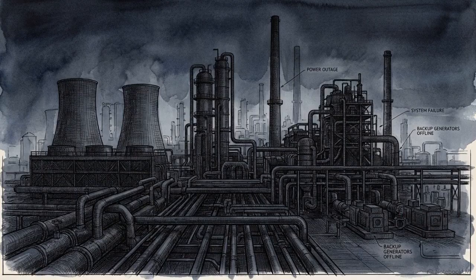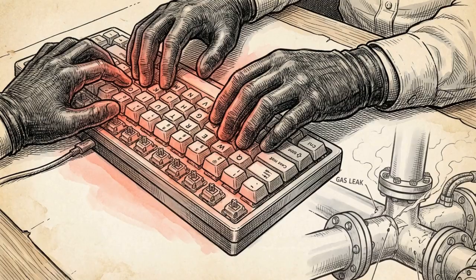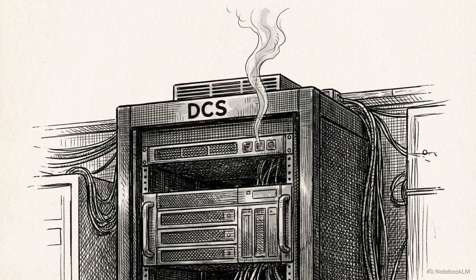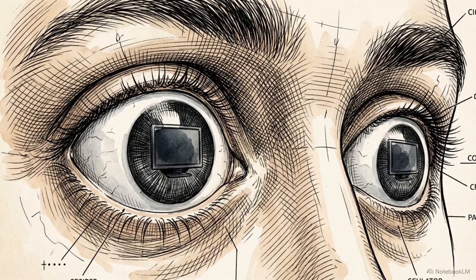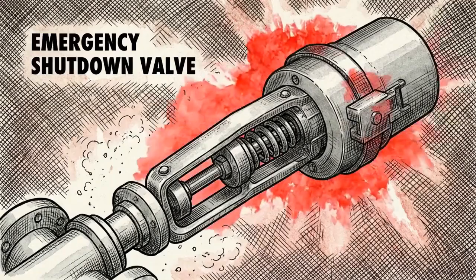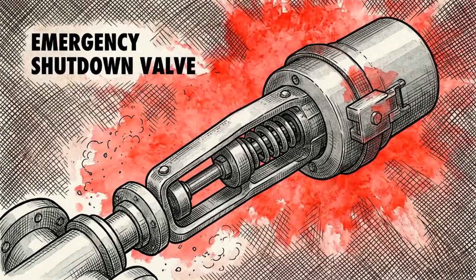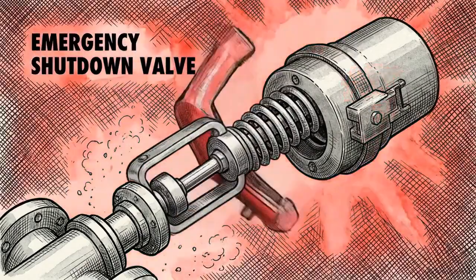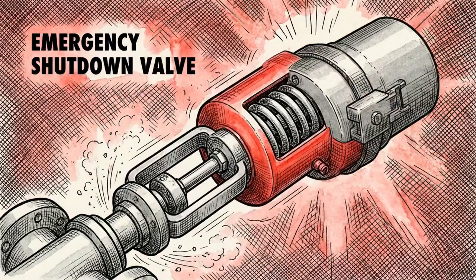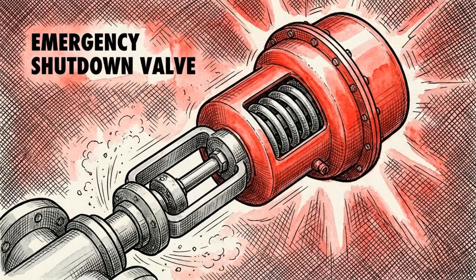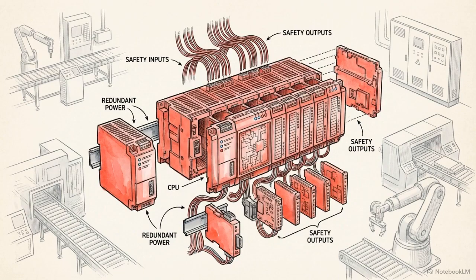A power loss, a severe software bug, or a targeted cyber attack can cause the DCS to freeze or fail entirely. When the primary control system goes blind, an entirely dormant parallel network must instantly wake up, isolate the dangerous fluids, and safely shut down the facility before a catastrophe occurs. This secondary network is the Safety Instrumented System, or SIS.